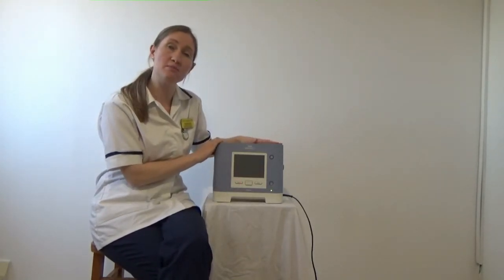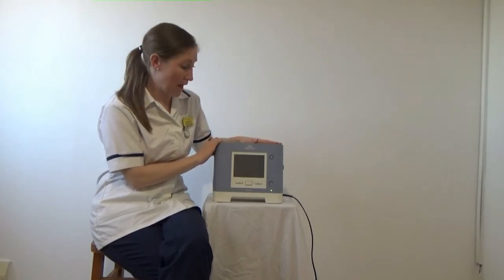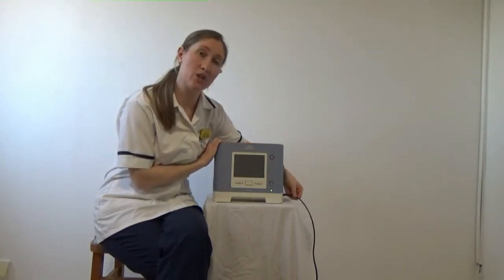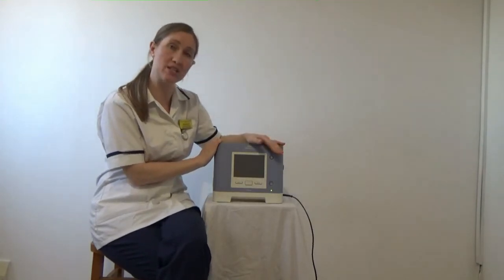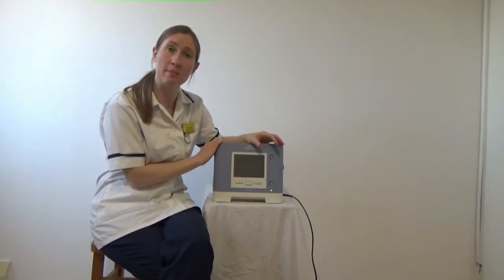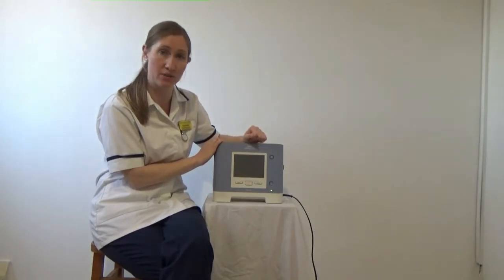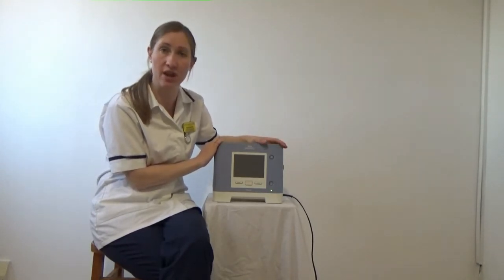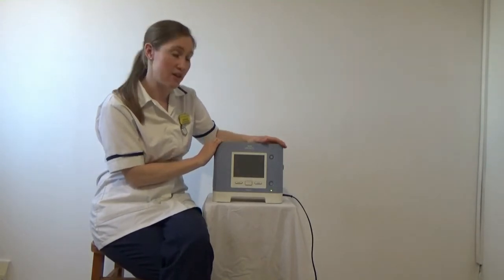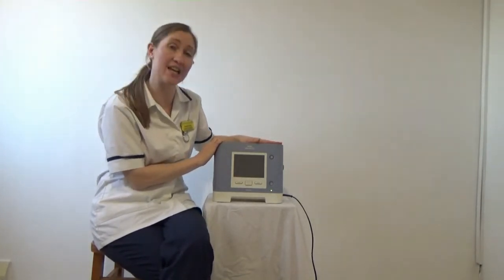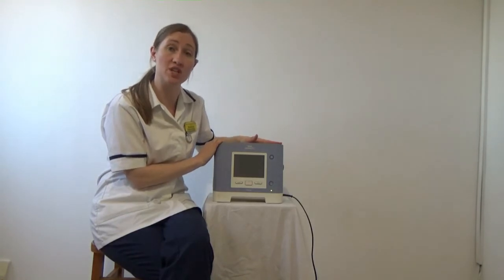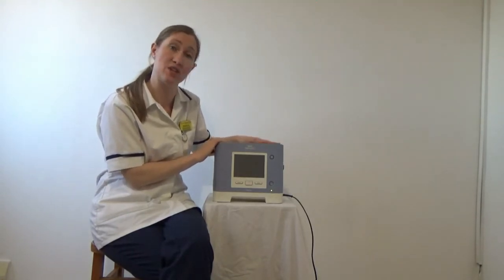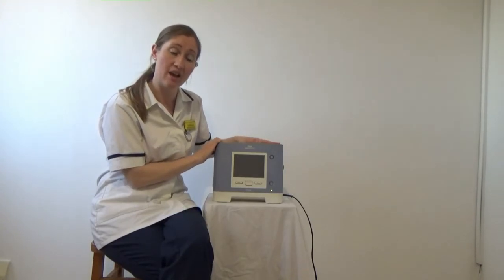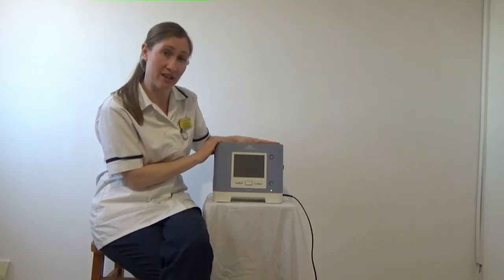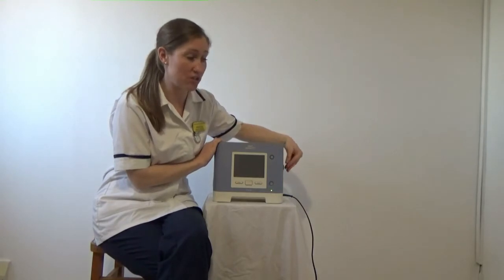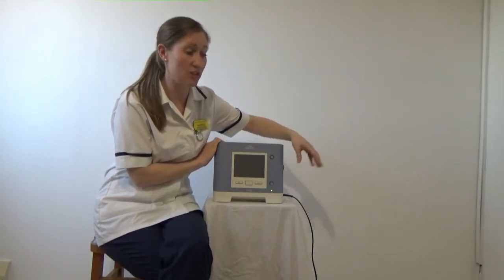High priority alarms include loss of power, in which case just check your power connection, check that the plug socket is switched on, and if you have any concerns about the plug socket, you may wish to try a different power source. If the problem continues, contact your NIV department. Another high priority alarm is ventilator inoperative, in which case I would suggest you contact your NIV department as it sounds like your ventilator needs replacing.